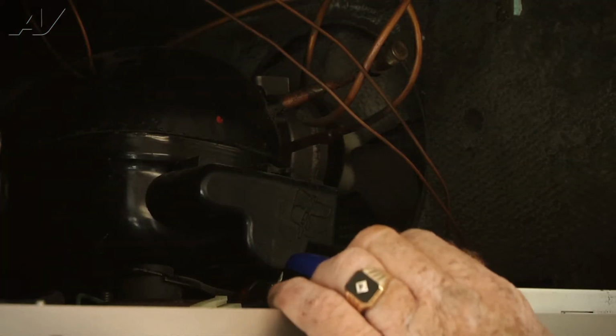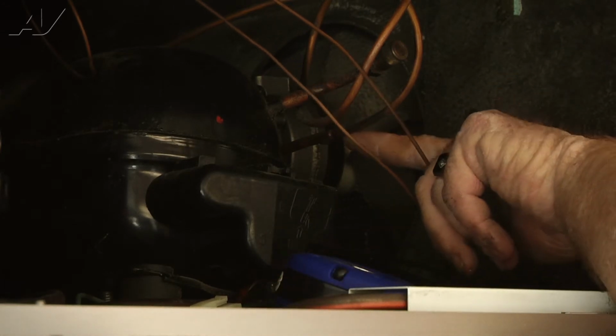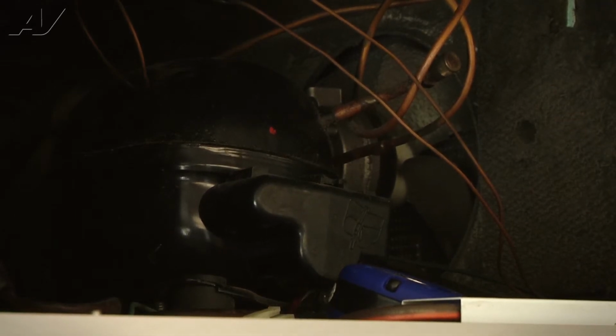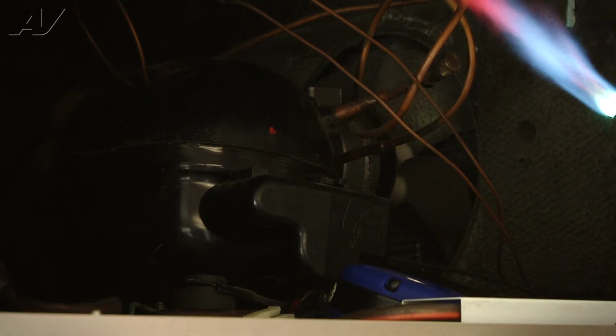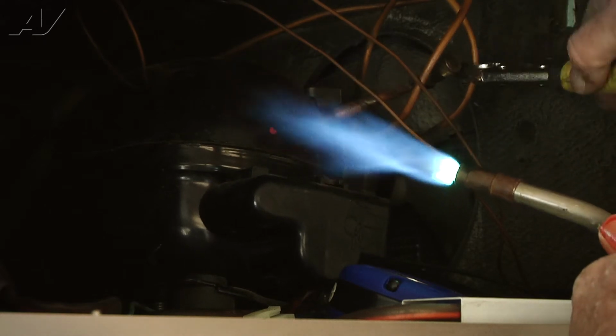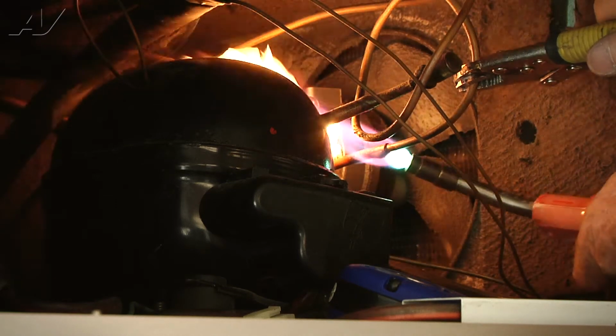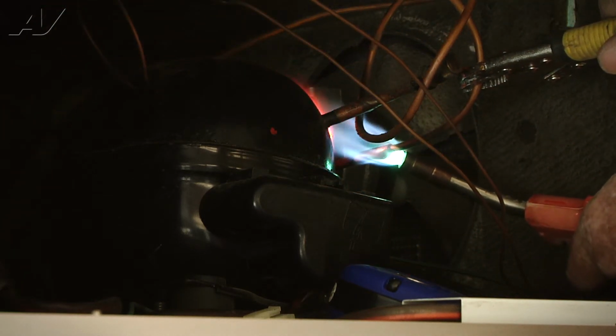So now the same thing, you're going to set your tubing cutter on the pipe. Make sure that where you set it, you have clearance to rotate it around. Tighten it down, snug, and start to rotate. Now at this point, we're going to get our torch and we are going to unweld the high side connection here. Get our torch going. And our vice grips so we don't touch the hot metal. And I'm going to put the vice grip around the tubing and then get the torch on the welded connection.